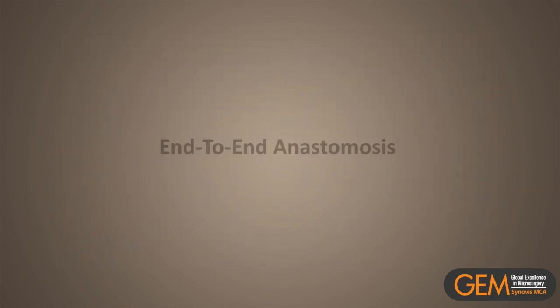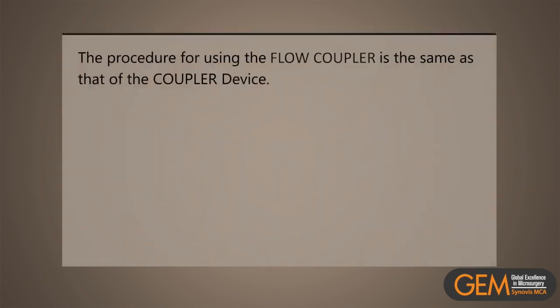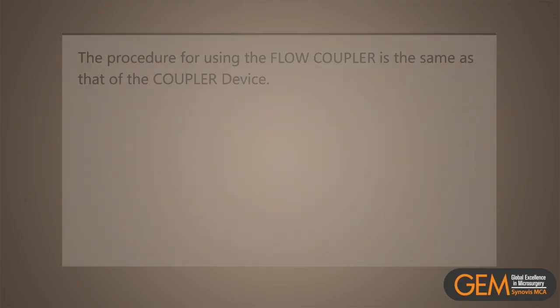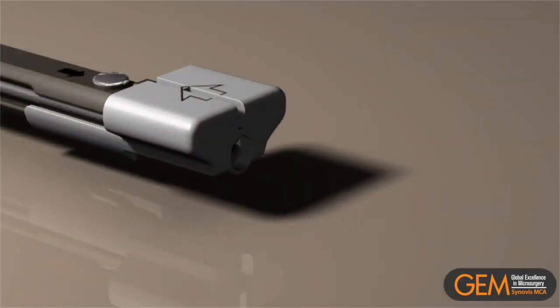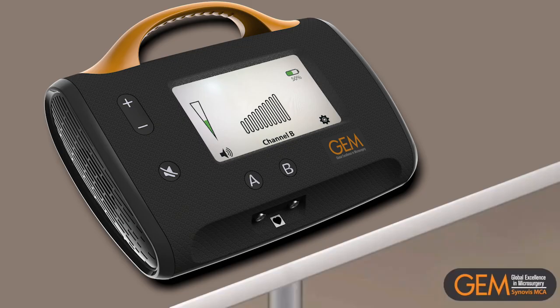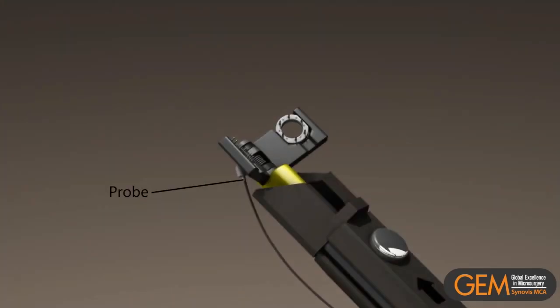End-to-end anastomosis. The procedure for using the flow coupler is the same as that of the coupler device. After matching of indicator arrows between the anastomotic instrument and the flow coupler has been verified by an audible click, verify probe function by connecting the probe to the monitor and irrigating the attached probe tip with sterile saline solution. An audible signal from the monitor verifies proper function of the device.